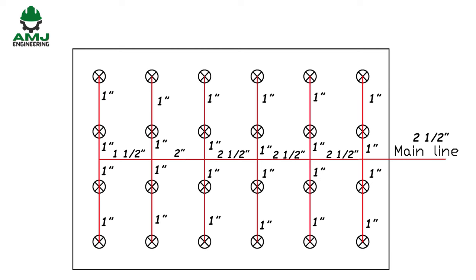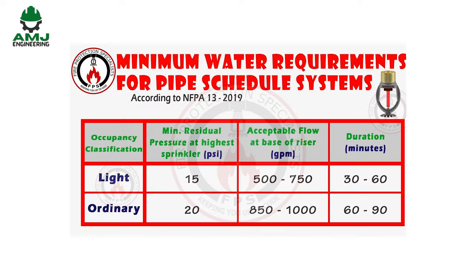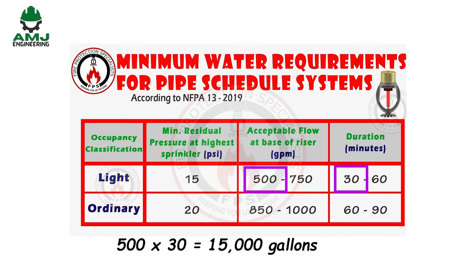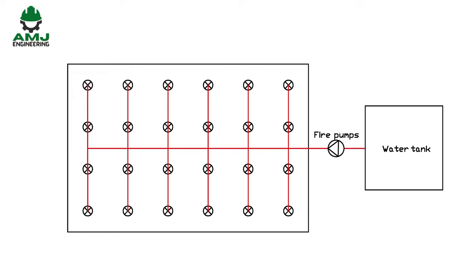What is the minimum water supply requirement for pipe schedule systems? The table below summarizes the minimum water flow rate, residual pressure, and duration of pipe schedule systems. Therefore, 500 GPM multiplied by 30 minutes means a minimum of 15,000 gallons water tank shall be constructed.